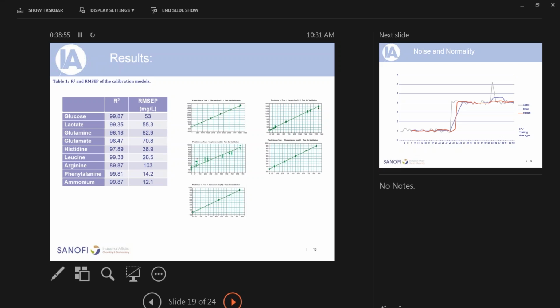Phenylalanine I talked about, ammonia we can measure. The one we really struggle to measure is arginine. I believe that probably reflects something more complicated going on with arginine rather than a weakness in the Raman scatter. I think there's some sort of concentration dependency, that the spectrum changes. When I look at that curve there's almost some sort of residual error shaped like a sigmoid curve, but I don't know, I speculate, and I raise it because the subject is of interest to me. We haven't got to the bottom of why that occurs or why arginine is uniquely difficult to quantify, but we have a calibration that would satisfy our requirements at least.